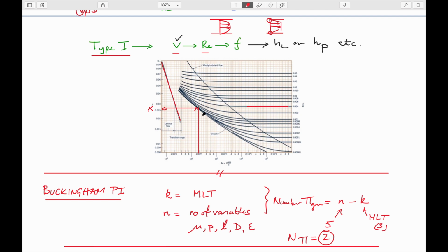If it's a smooth pipe, then it varies along this line here. If it's a given roughness, relative roughness, then you control it based on these numbers here. These are very rough pipes. These are not very rough pipes. And you can determine the magnitude of this friction factor. Importantly, I guess, if it's high velocity, then the friction factor is a given magnitude, and it doesn't change versus the rate of flow within the pipe. So the calculations are typically maybe a little bit easier.